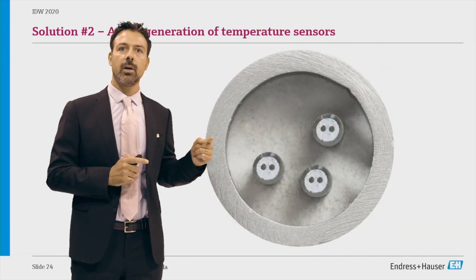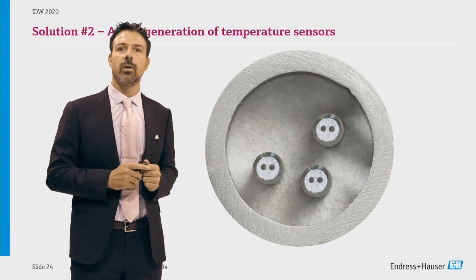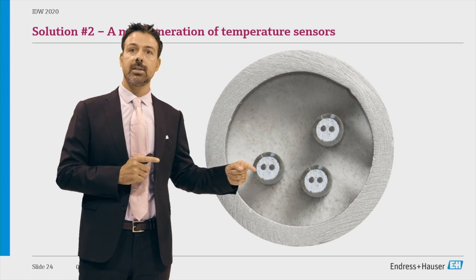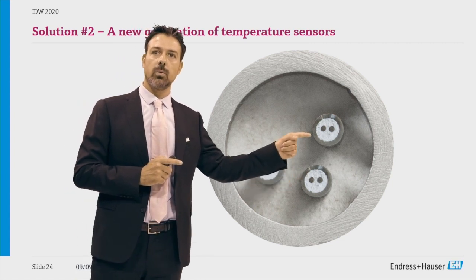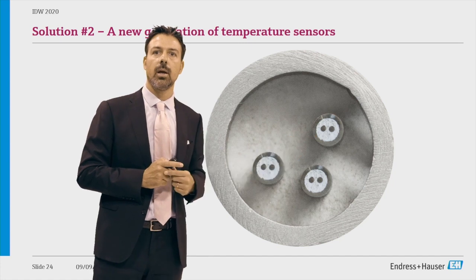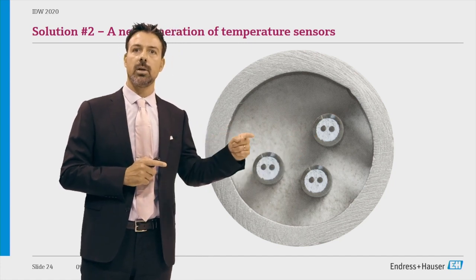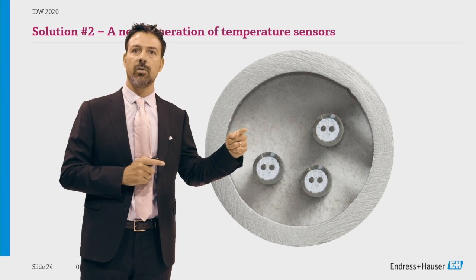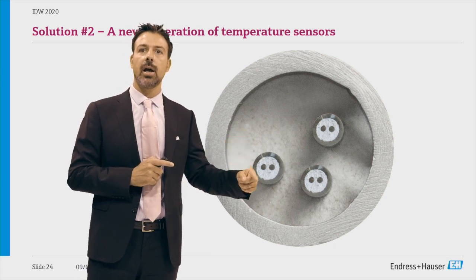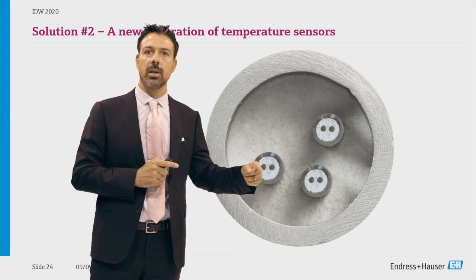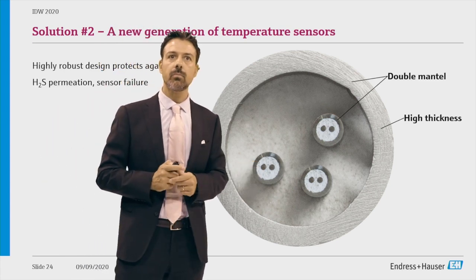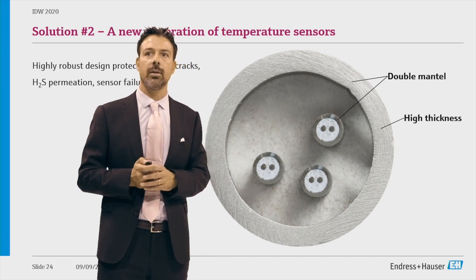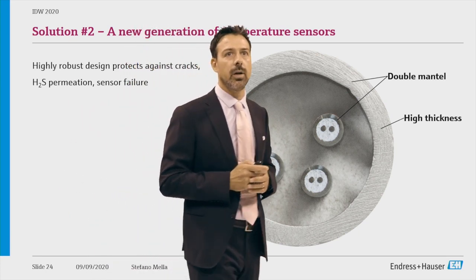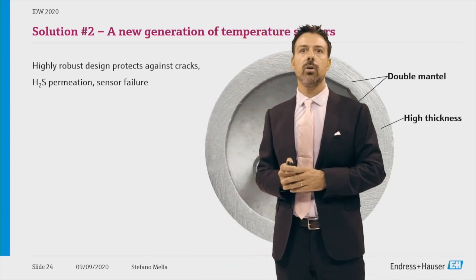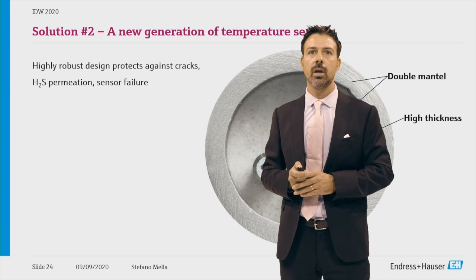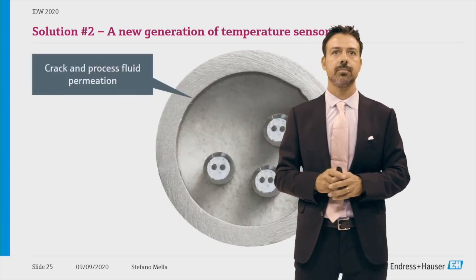So we have an outer layer or outer mantle of the temperature sensors, and inside we have additional layers, one per each dedicated thermocouple. And we also have double insulation material. So here we have an outer mineral insulated layer, and each sensor has its own mineral insulated material. In other words, we have double mantle and higher thickness, which leads to a highly robust design, able to avoid cracks, H2S permeation, and premature sensor failures.